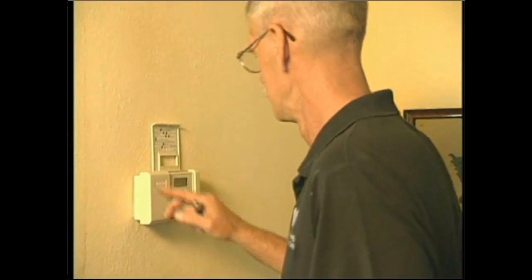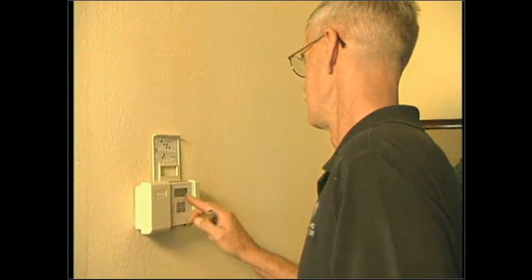So you're trying to get a real-world testing environment — not rearranging everything in the house, but understanding the parameters you're dealing with. Yeah, because if large pieces of furniture restrict the air flow on the return, I ought to be able to document that so I know why my testing might be a little different than it should. I'll also document the thermostat settings so I can return the home to the condition I found it. Good communication is the key.